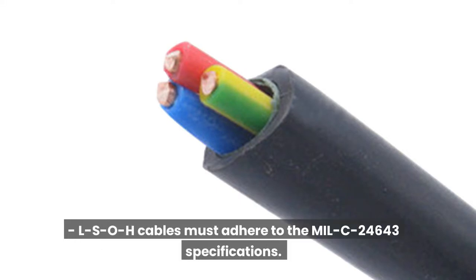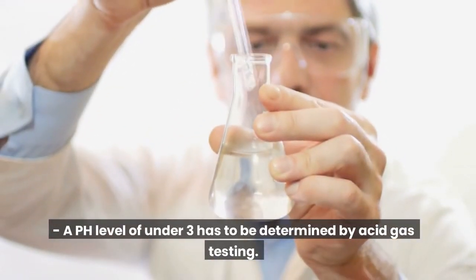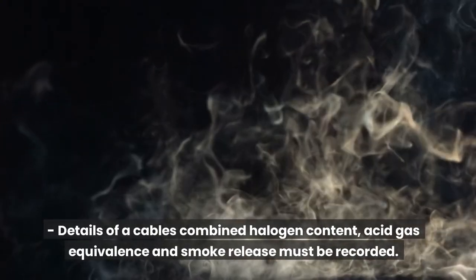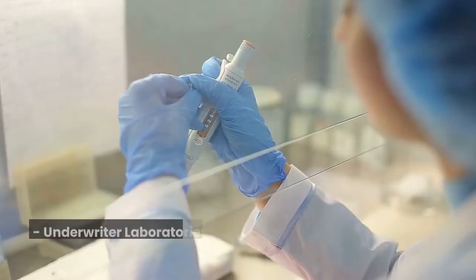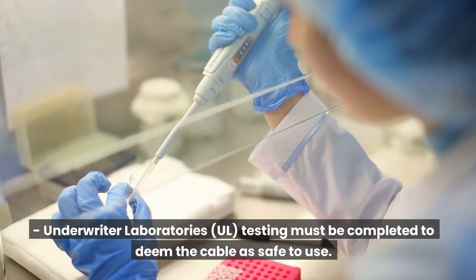What are the testing procedures for LSOH? LSOH cables must adhere to the MIL-C24643 specifications. A pH level of under 3 has to be determined by acid-gas testing. Details of a cable's combined halogen content, acid-gas equivalence and smoke release must be recorded. Underwriter Laboratories UL testing, testing must be completed to deem the cable as safe to use.